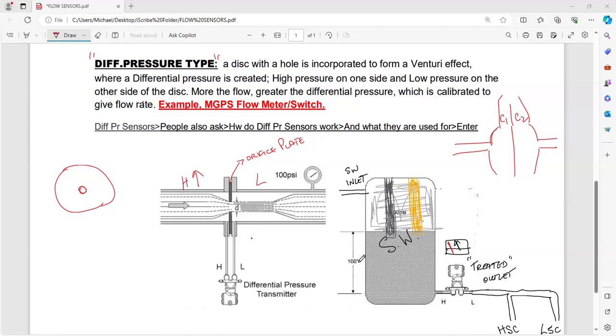Because see, anyway, that pipeline coming into your scrubber is not a narrow pipeline. It is quite a big pipeline. The flow is driven by a pump, and that pump is a dedicated pump for your scrubber. Maybe they will have one, but you don't need that. What you're going to have is that particular flow thing, which is not exactly a flow meter, where you'll be having it going into your deck seal. That is only an indication of whether there is flow or not. That's all. It's not giving you a flow rate, because that is basically just a flap telling you, yes, water is going into your deck seal.